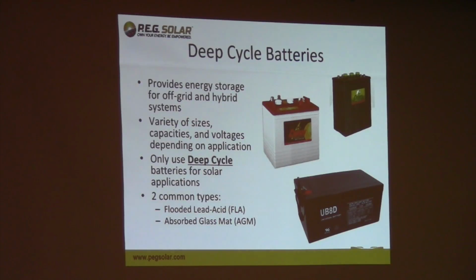So the question was, if you use traditional flooded batteries, do you have to put some kind of heating system or climate control to keep them healthy? It really depends. In areas with extreme cold, like Alaska or the Dakotas, it's important that batteries are climate controlled. Here in Virginia, where we don't see temperatures much below freezing, we've put systems in where batteries operate outside. There is a performance hit in very cold temperatures, but it's not necessary to climate control it. Ideally, though, a sealed battery inside the home that takes advantage of the home's climate control will perform better.